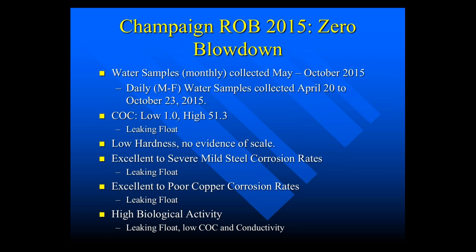Now we're into 2015 with zero blowdown. Water samples were collected monthly May to October, but we also collected samples daily Monday through Friday from April 20th through October 2015. The cycles of concentration ranged from 1 to 51.3. They were down at 1 cycle of concentration because of a leaky float. We had low hardness with no evidence of scale. Mild steel corrosion rates ranged from excellent to severe — the severe rates were caused by the leaky float. Copper similarly ranged from excellent to poor, also due to the leaky float. High biological activity was observed, linked to low cycles of concentration and conductivity caused by the float problem.